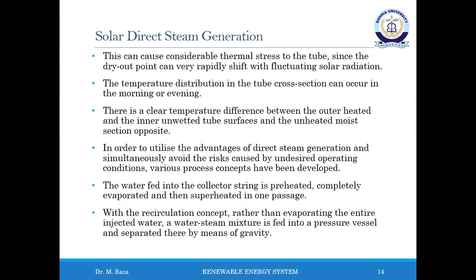This concept is very robust but incurs higher cost as a result of the necessary pressure vessel, the circulation pump, and the losses in the recirculation system. Because cheap steam storage systems are not yet available, solar direct steam generation is initially more suitable for smaller systems or hybrid power plants that combine solar and fossil energy.